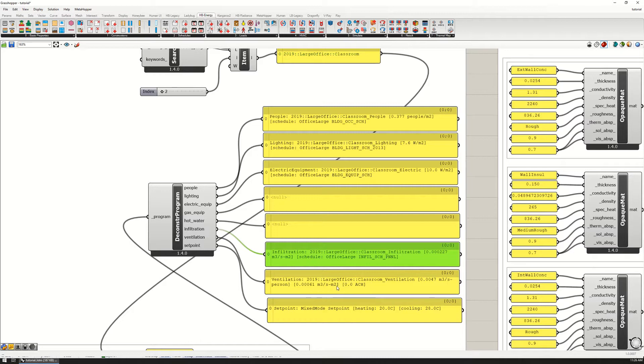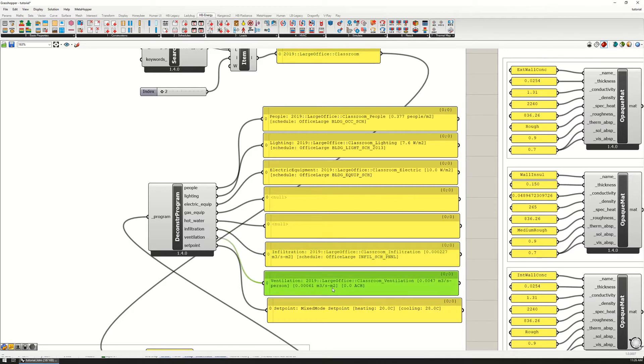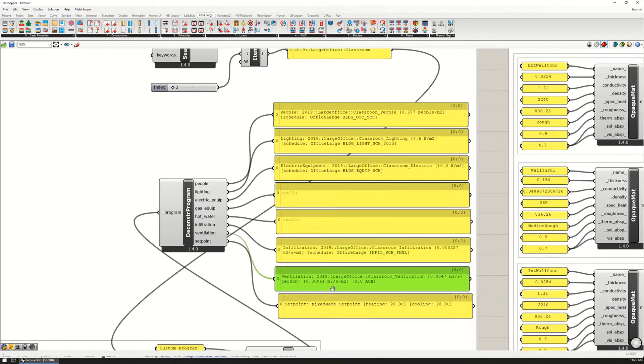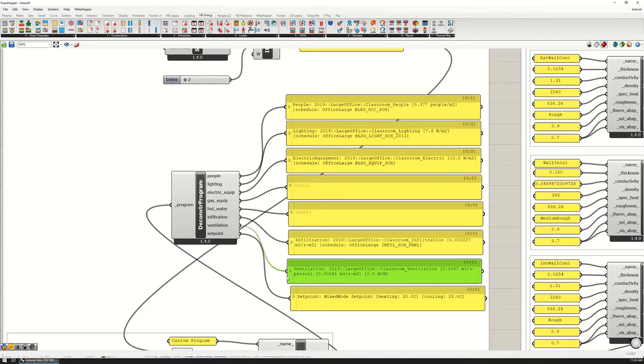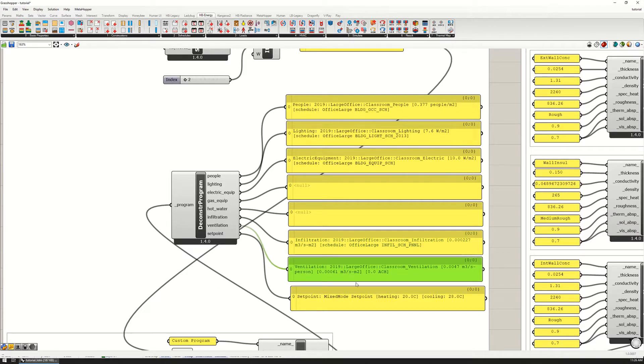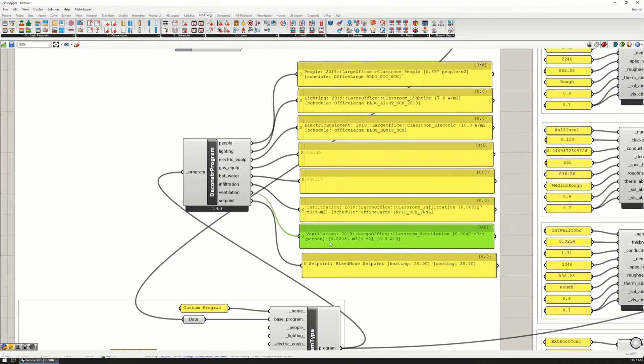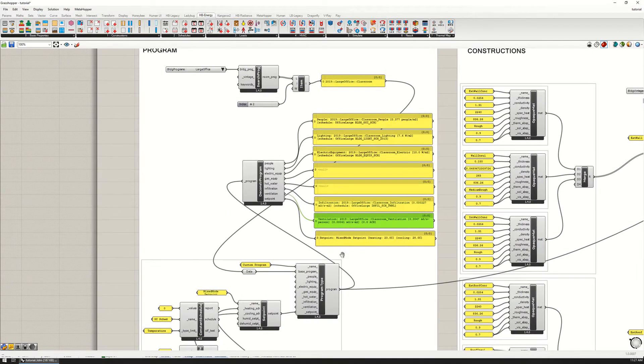The terms change, so it's 0.0047 per person and 0.0006 per square meter. This is a fairly common way of setting ventilation based on both the number of people, the occupancy, as well as the area of the building.